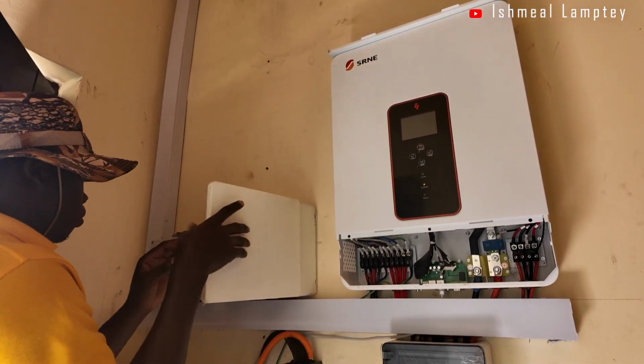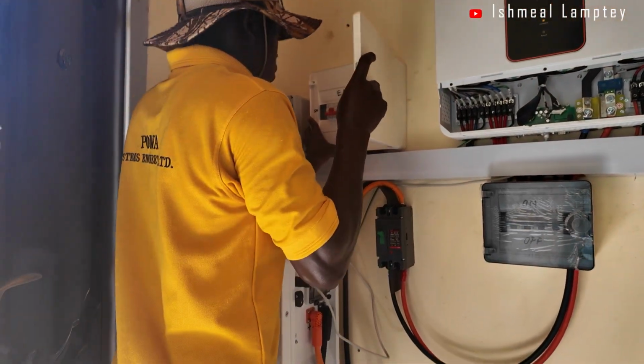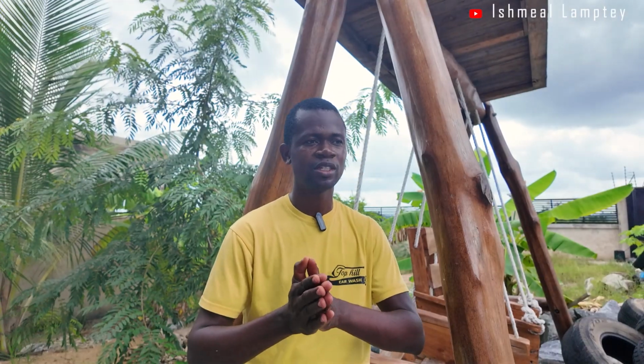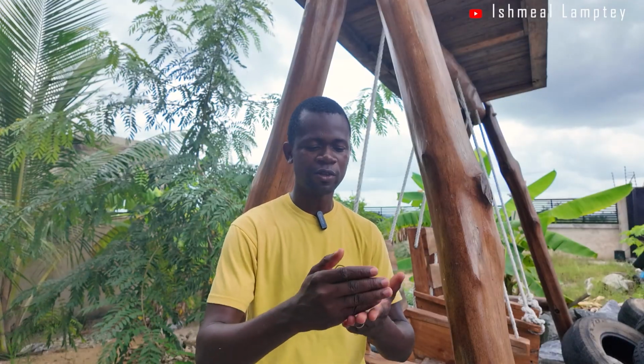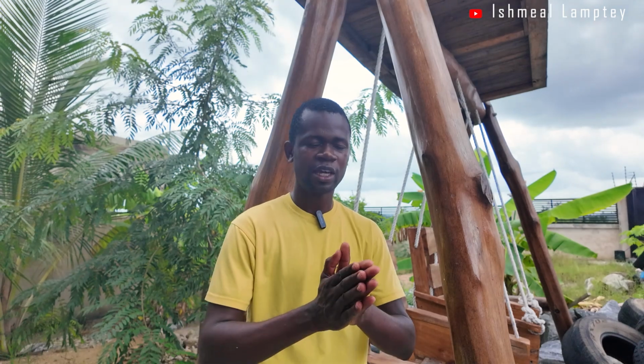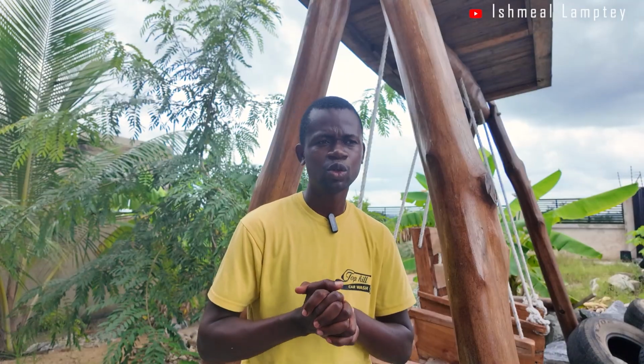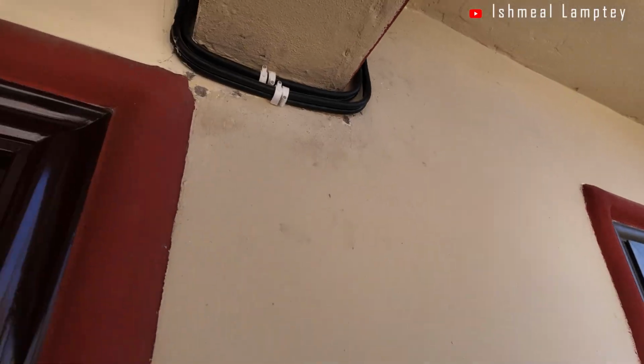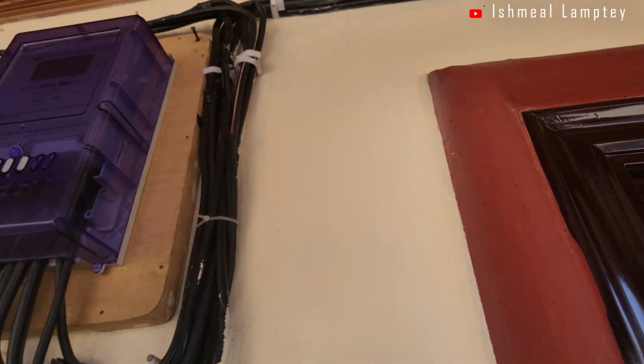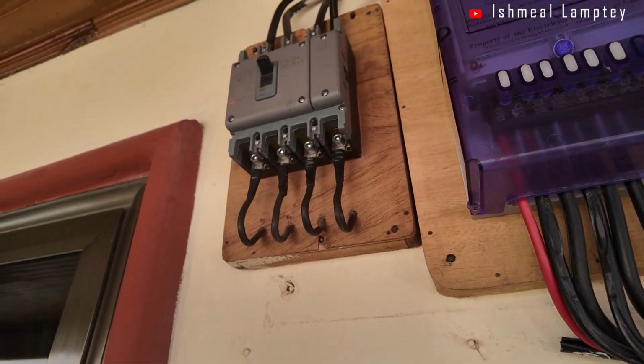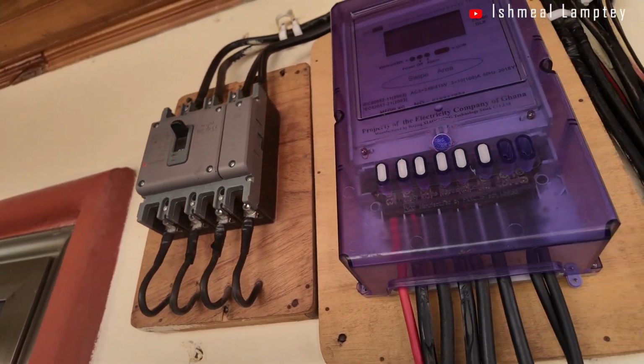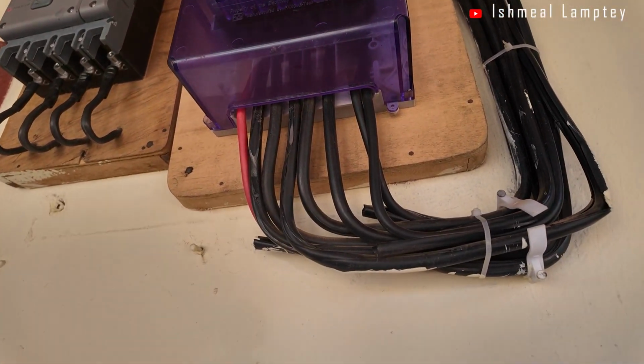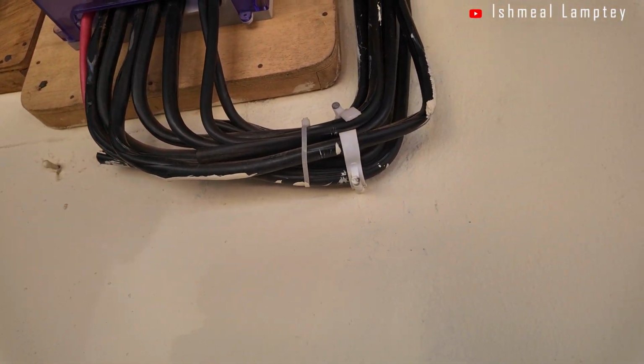Aside from that, also there was an error, which is phase error. Now, phase error means that because we have 3 phases, one of the phases is either not configured properly, and we had configured exactly what was done by ECG, and we're still getting the error. So upon further trace, we realized that ECG didn't really follow the way they are supposed to do it. So if there's L1, L2, L3, it has to be in that pattern. So they had missed both L2 and L3, so we had to correct that. Then after that also, we ran into another problem.